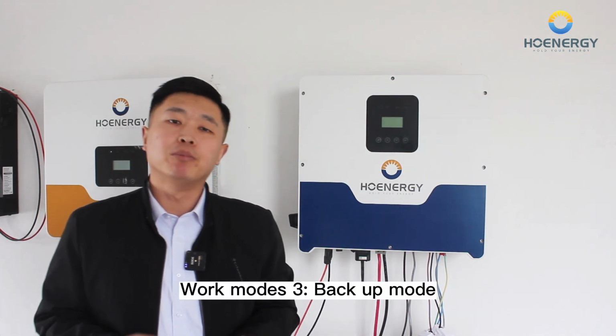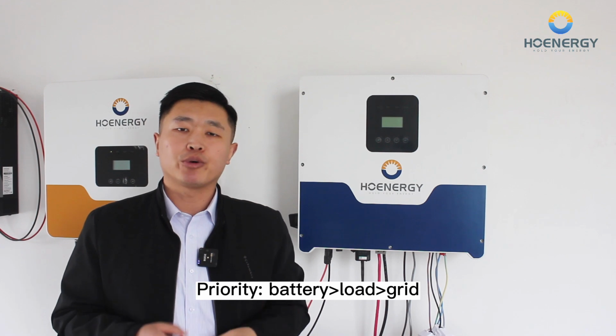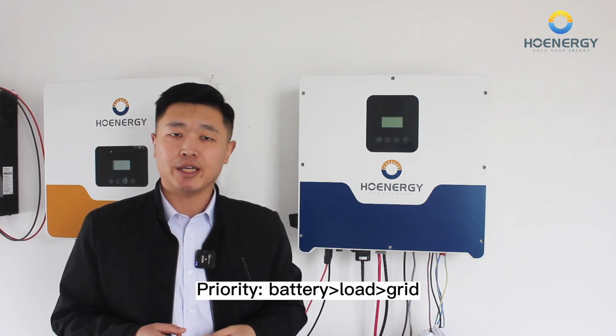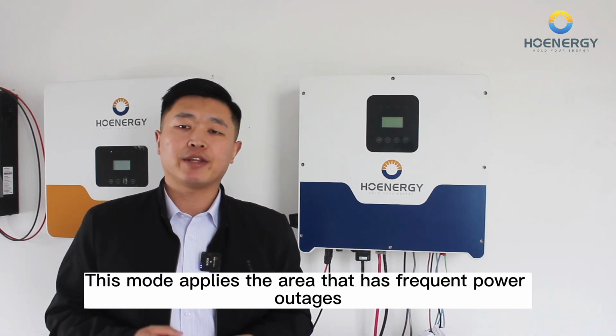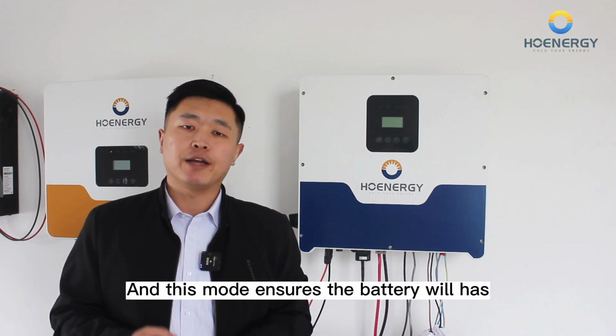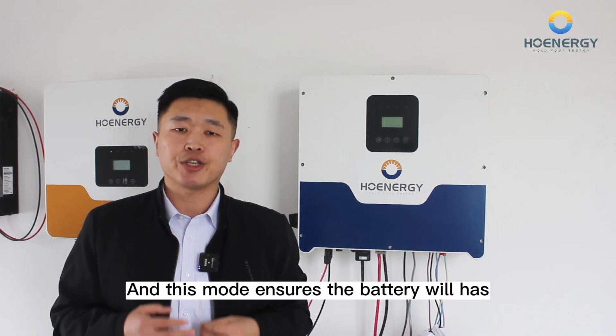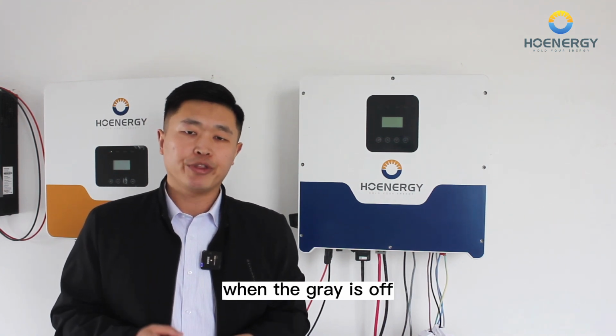Work mode 3, backup mode. Priority: battery greater than load, load greater than grid. This mode applies the area that has frequent power outages, and this mode ensures the battery will have enough energy to supply when the grid is off.